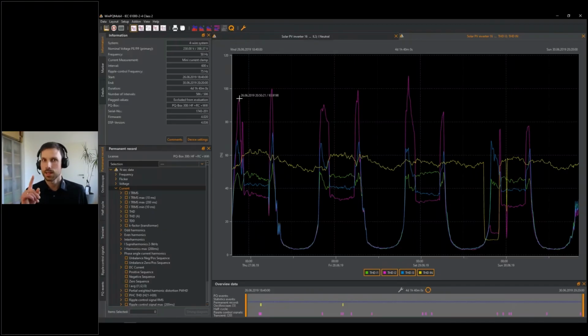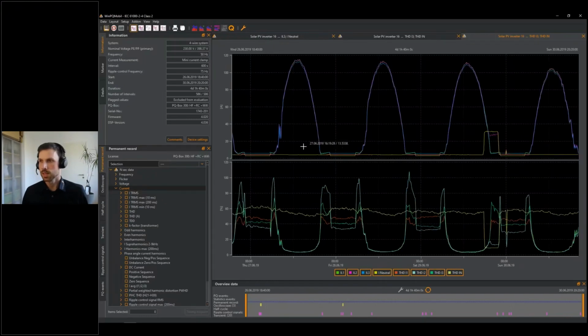Well, now you have to consider that the value in percent is in percent of the fundamental. So if I check both values, the THD and the true RMS value, I see, okay, I got distortions over here at around 100%, but the current was quite low.